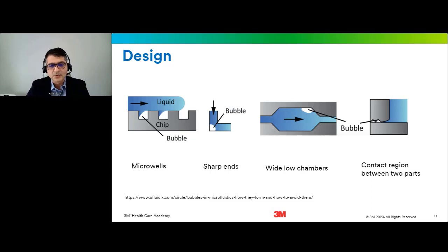Let's have a look at the design component. The design of new devices sometimes may not allow liquid cleaning agents and disinfecting agents to reach all areas within medical devices. As I mentioned, new devices are being made for minimally invasive surgeries and other applications, and the complexity of devices increases daily. In some of these designs, air may be trapped in corners, microwells, and contact regions between two components. If that happens, it can prevent contact with liquid disinfectants and not allow proper disinfection. So some of the problems might be related to design.